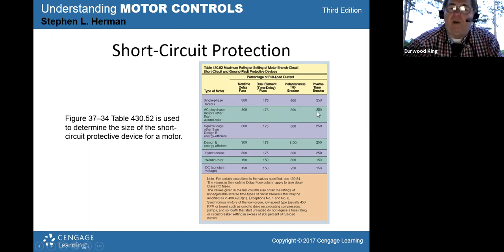So if you got a breaker that's ahead of a starter, on top of a starter, you can take the amp rating of the motor and multiply it by 2.5. That's 250%. And that's your highest rating for a breaker that goes ahead of the starter. You don't have to go that high. I personally would not go that high, but you're allowed to go that high if it's actually a breaker that's ahead of the starter instead of a fuse.